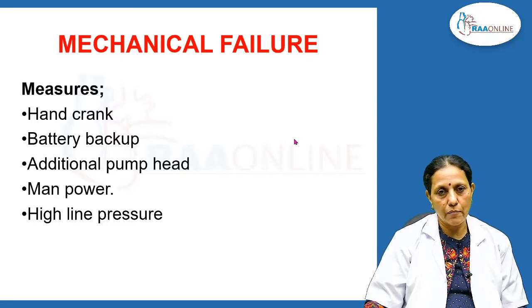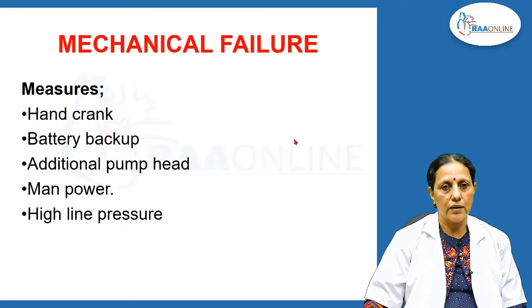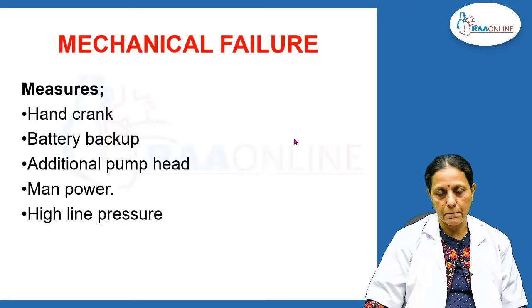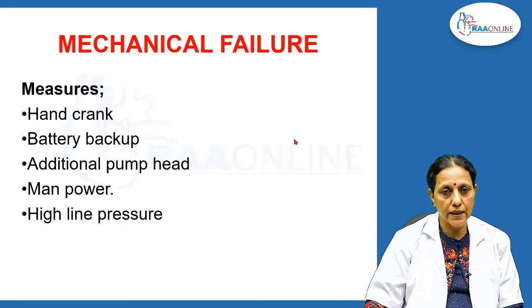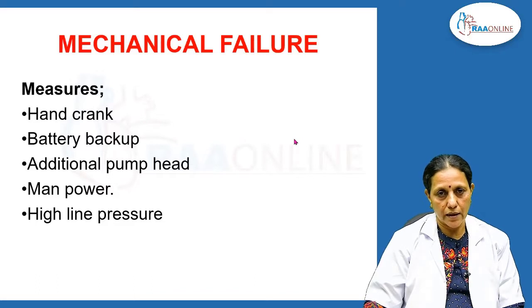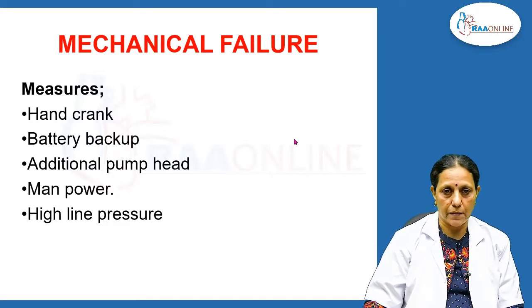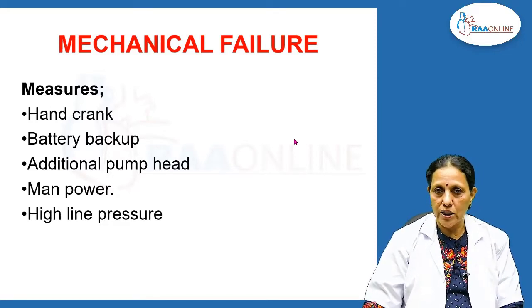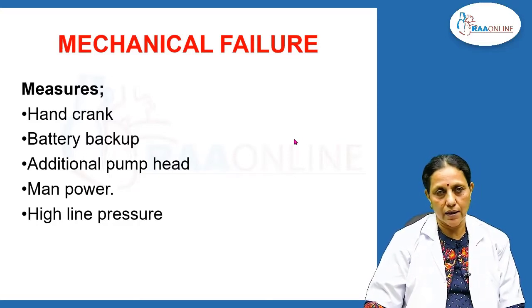Secondly, if there is no battery backup, this can be done. Pumps which have battery backup will take over the situation for a few minutes. Another option is you can have an additional pump head. Suppose there is some major problem inside the pump, maybe the motor or the belt, where the hand crank does not work, you need to have an additional pump. You can change the tubings from the non-working pump to the other pump and start running. So, whatever the way is, you should keep the flow going.